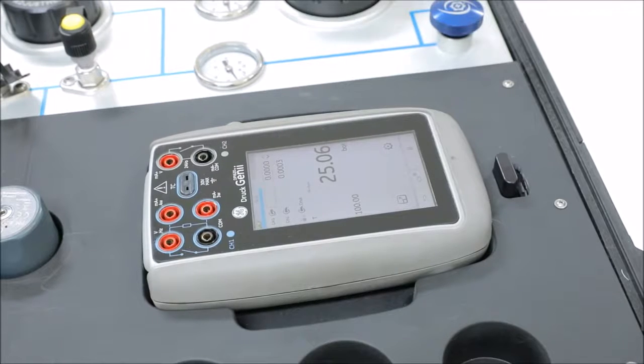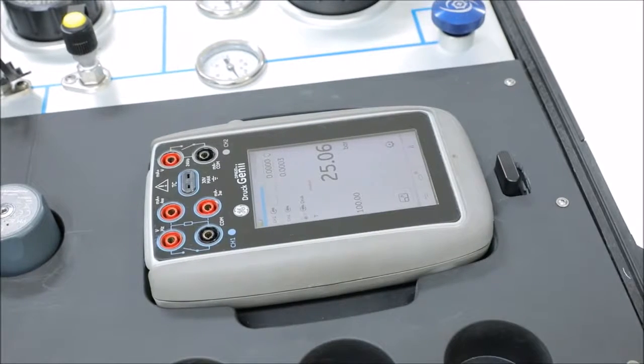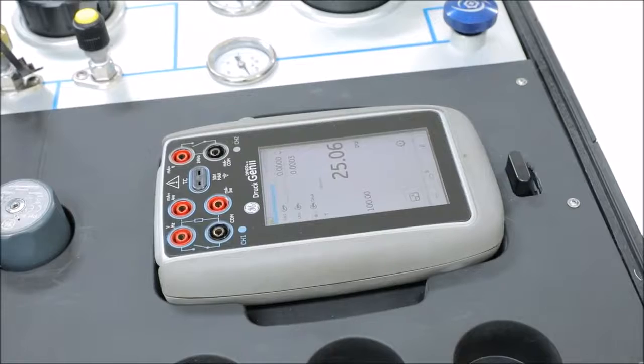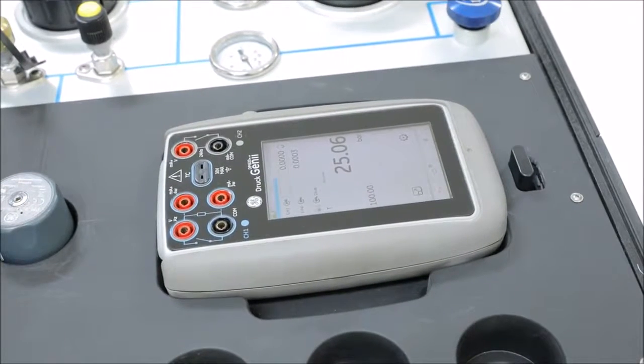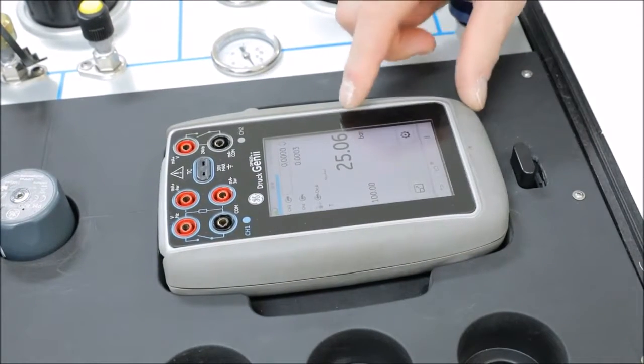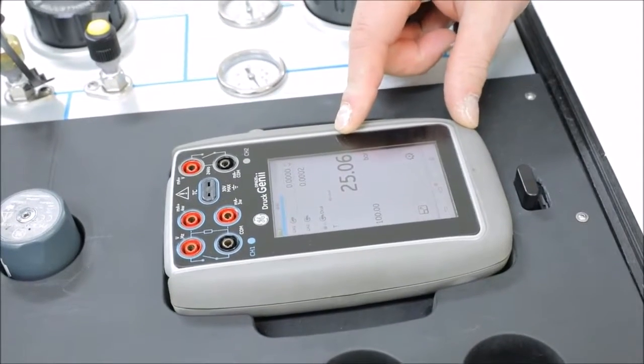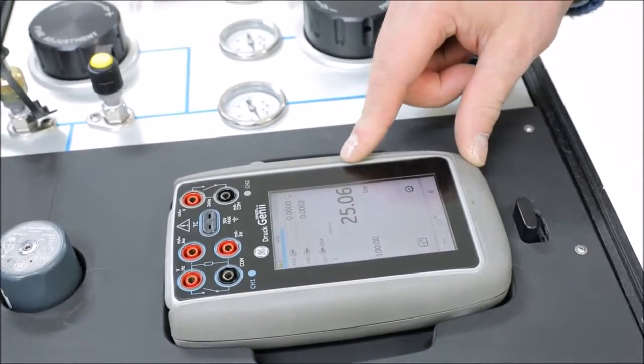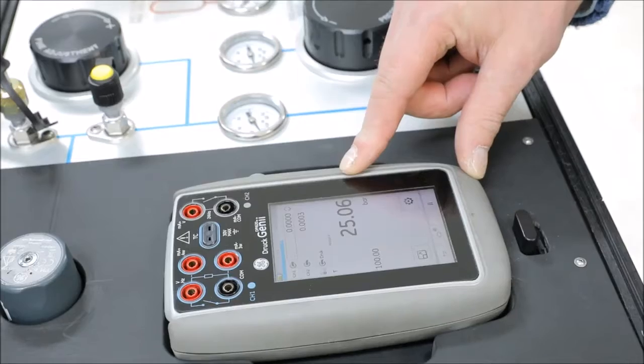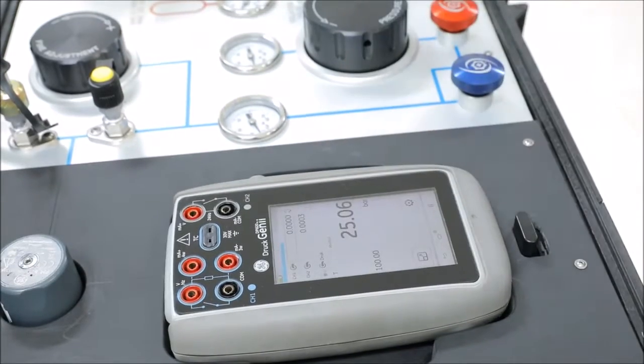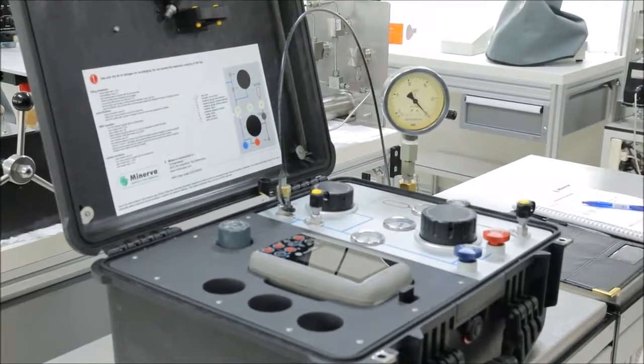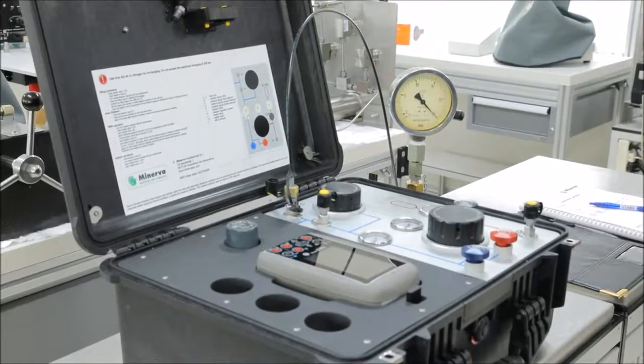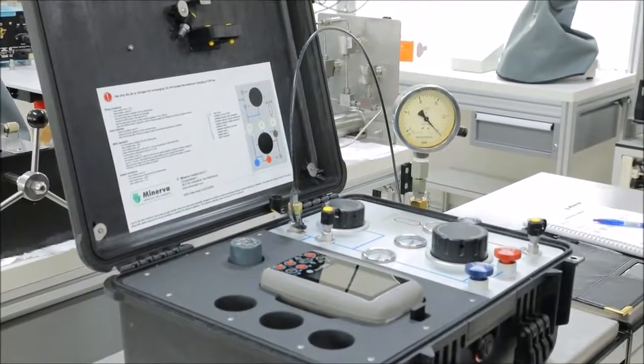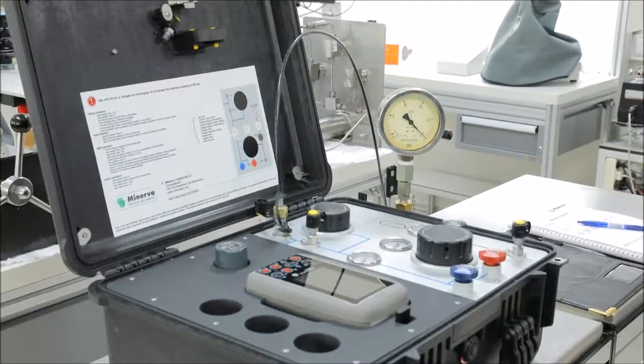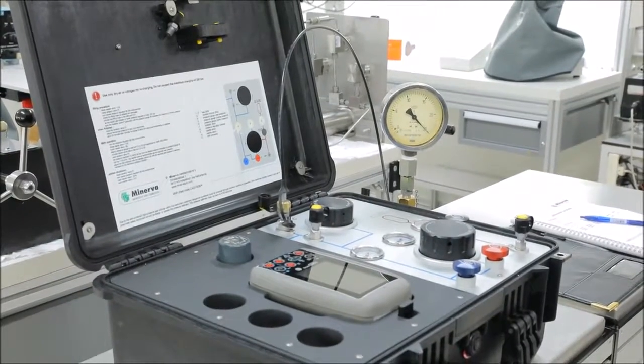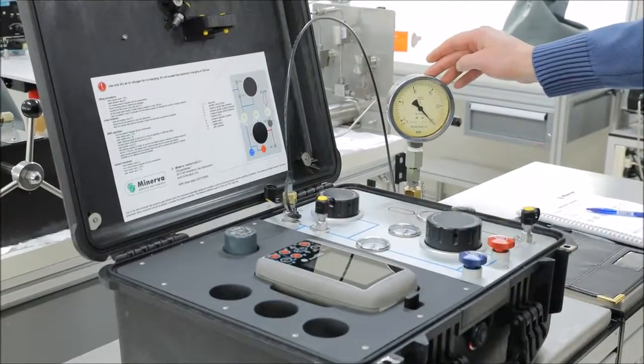After waiting for a short period of time to eliminate any adiabatic effects in my system, I will check the readout of my device under test, and I see it's absolutely not changing, so no leak, ready to start the calibration. Our calibration system passed the leak test, so we're ready to start the calibration. Remember, we're still at 25 bars.